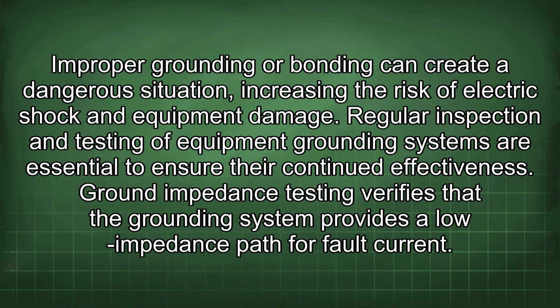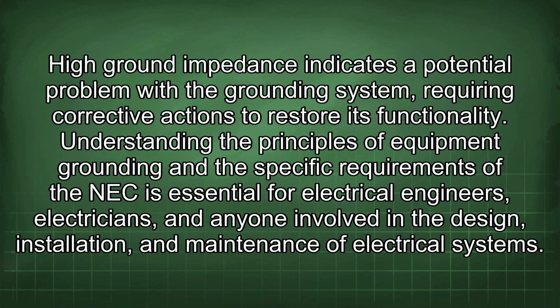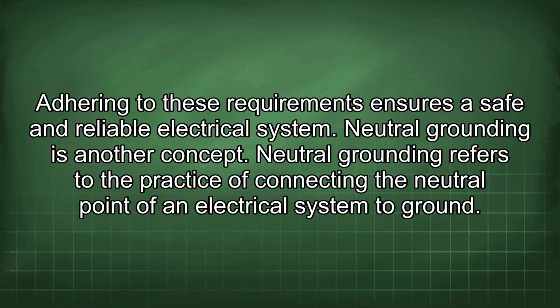Regular inspection and testing of equipment grounding systems are essential to ensure their continued effectiveness. Ground impedance testing verifies that the grounding system provides a low impedance path for fault current. High ground impedance indicates a potential problem with the grounding system, requiring corrective actions to restore its functionality. Understanding the principles of equipment grounding and the specific requirements of the NEC is essential for electrical engineers, electricians, and anyone involved in the design, installation, and maintenance of electrical systems. Adhering to these requirements ensures a safe and reliable electrical system.